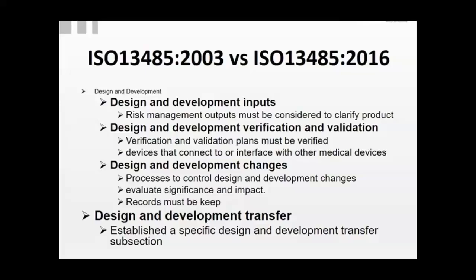Design and development changes. One of the differences now from the 2016 model is that a process to control design and development changes must exist. You have to evaluate significance and impact. So in other words, if you make a change in the design and development, you have to now evaluate the significance of that change, what it did, and how different it is, and the impact it would have to the final product. And these have to be documented processes. You have to have a process now in place to be able to do this. And you have to keep records. That's another element added to the design development changes into the standard.